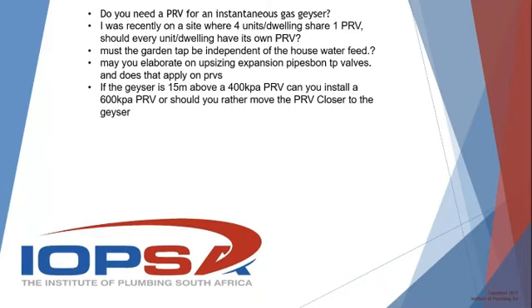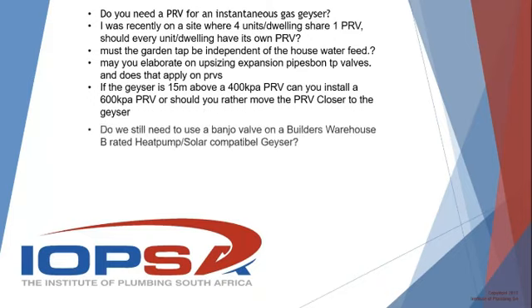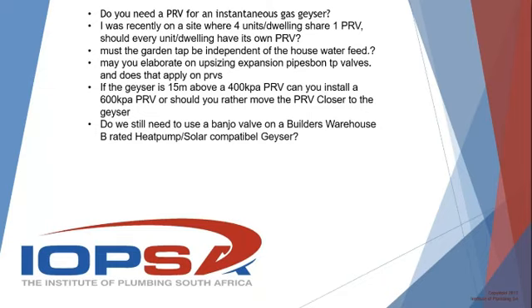As to whether you can just put a 600 kPa in, it all depends on what the rating of the geyser is that you've got in there. You're not allowed to put a 600 kPa pressure control valve on a 400 geyser, even if you are going to be losing that pressure. So you'd have to rather take it much closer.